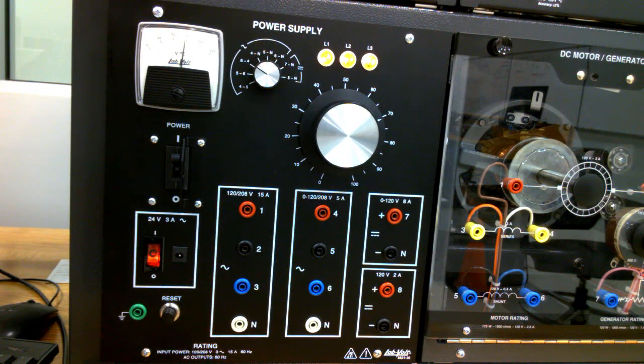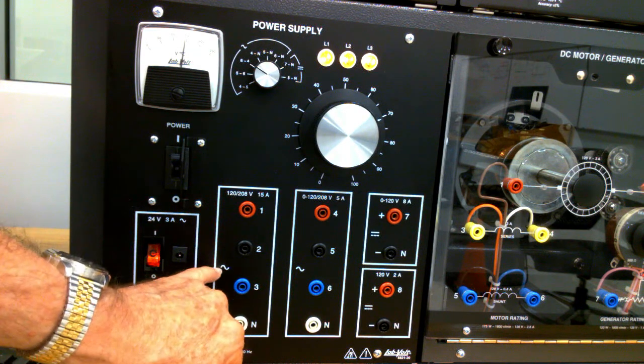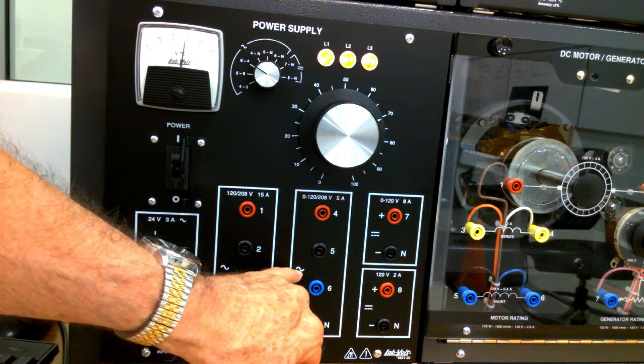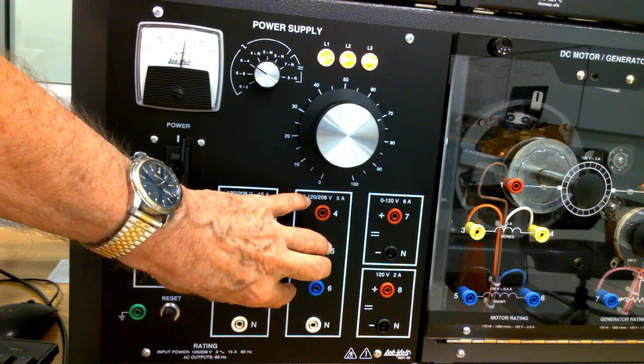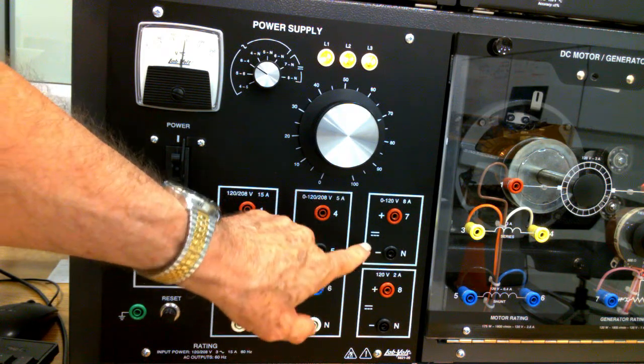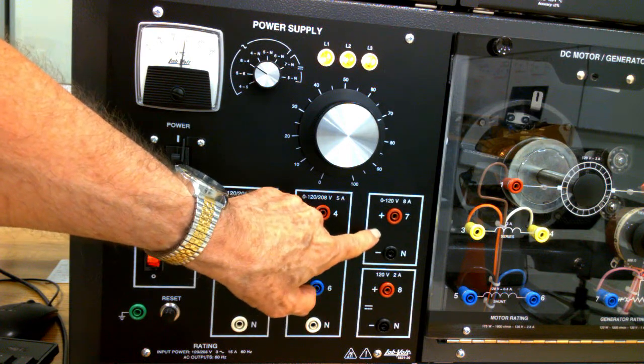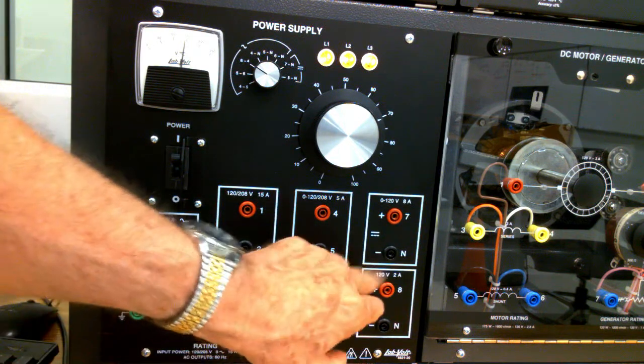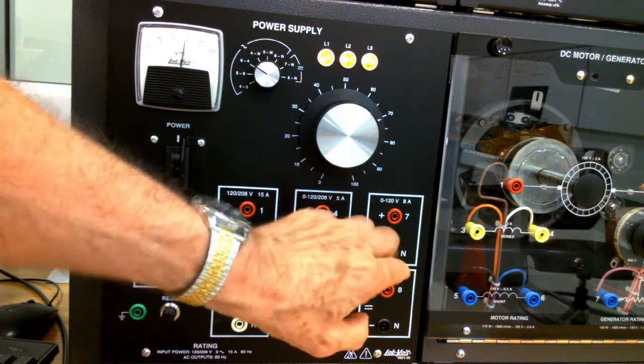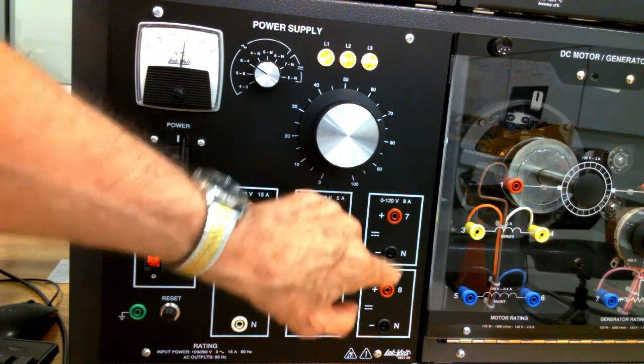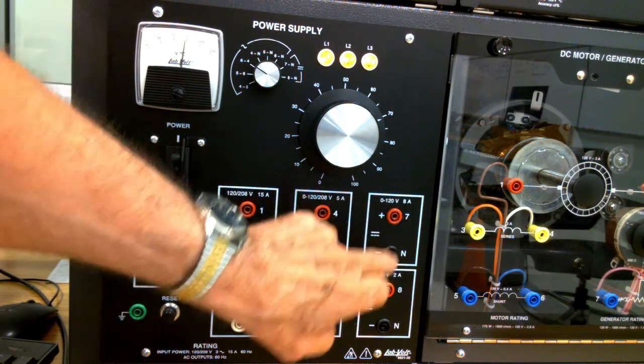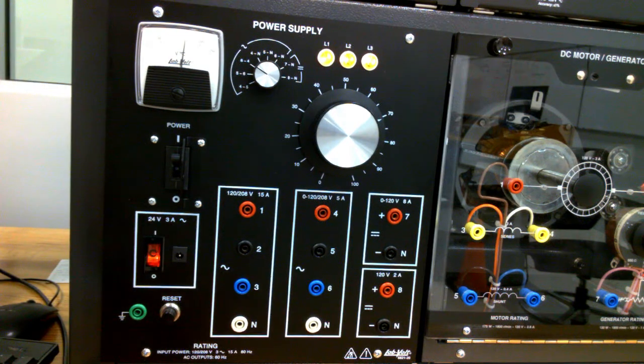Now then, if I want to, and by the way, let me say this one more time. The squiggly line represents a sinusoidal waveform, which means that these two are AC. Over here, you see I've got a dashed line with a solid line above it, and I also have a negative and a positive. So this is the DC voltage. So terminal 7 with respect to its neutral is 0 to 120 volts and good for 8 amps.